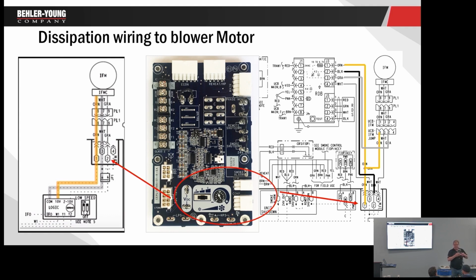Right here? Okay, this here where your motor's coming in. That's where they're tying that mitigation board in. I'm sorry, dissipation board. So instead of the orange wire just going to here, it's also making a U-turn and it's going up to this new dissipation board. Okay. And then the black comes to here instead of the gray. And then the gray comes from here to the motor. So what it'll do is instead of, like, you're going to remember all this here. Instead of the gray wire here going to the motor, it's a black wire going to the dissipation board.